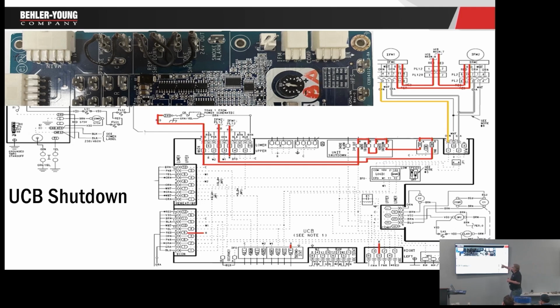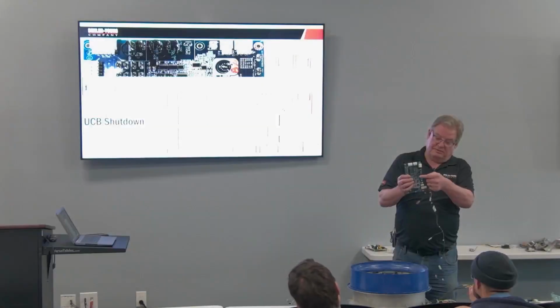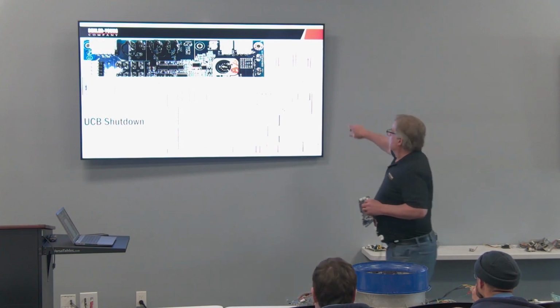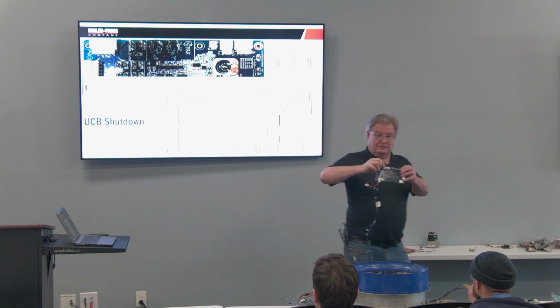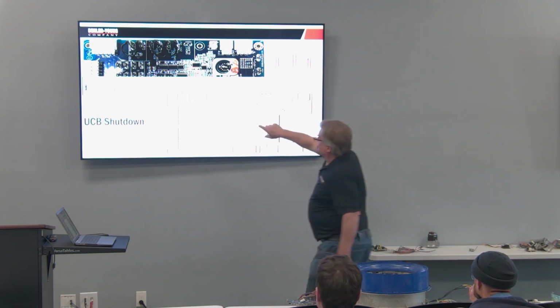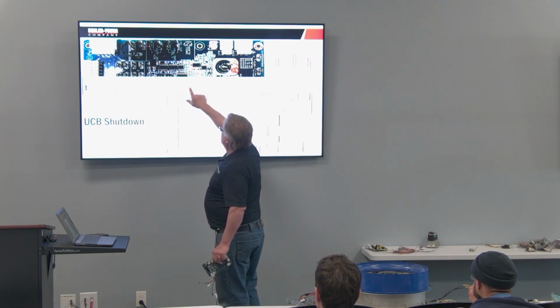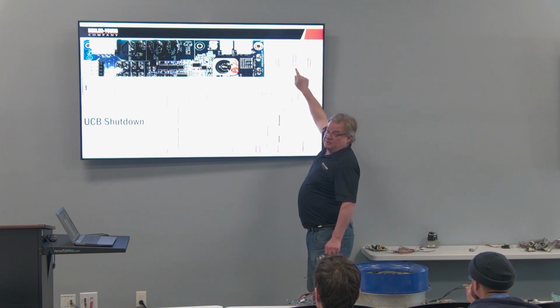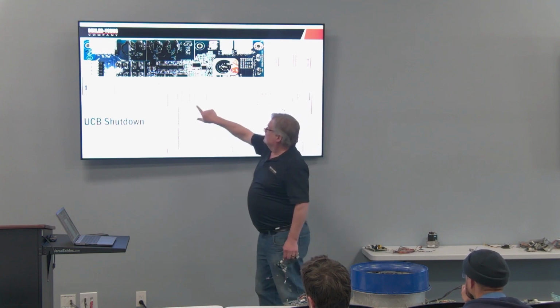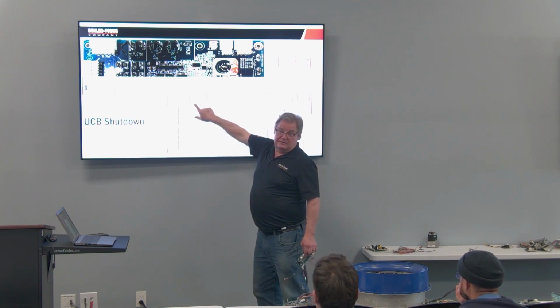So where it says 24 out, the bottom one there, it goes from here through this jumper, through this jumper, through this jumper. Then it goes back to the third terminal here, which is number 7, indoor fan motor. Oh, look at that. It goes through the safety relays in both fan motors. And it comes back on 7, and it goes to R. So what do you think it does then? Now it powers everything in the unit.